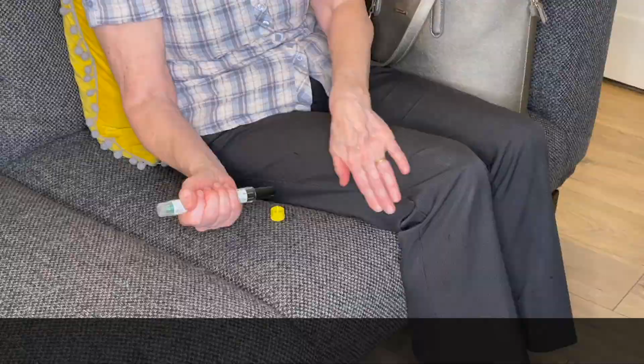Now, as I mentioned, there's 3 different types of Auto Injector Pens, and each of these types have a different time limit you should hold them for. The new EpiPens, it says to hold them for 3 seconds. The new jext, 10 seconds. And the new emerade pen, only 5 seconds. I suggest this is all very confusing, and you just hold them all for 10 seconds because you want to make sure that person gets that adrenaline into their muscle as quick as possible, and you don't want to delay that treatment, and you don't want to risk only holding a pen that's meant for 10 seconds for 3 seconds and wasting that time.